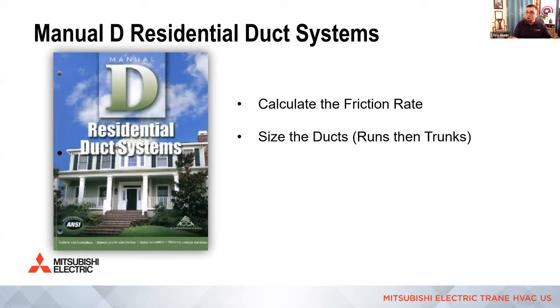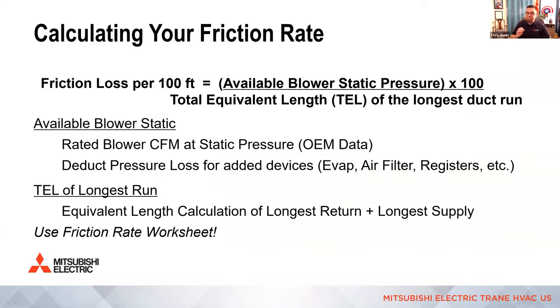We always do the runs first and then the trunks. And then, of course, we're going to verify velocity to make sure that even though we're getting the right volume of air there, it's not too noisy because it's moving too fast, or it doesn't mix in the room because it's moving too slow. So we're going to walk through these steps today and apply it to low static and mid and high static air handlers. All right, that's the key.